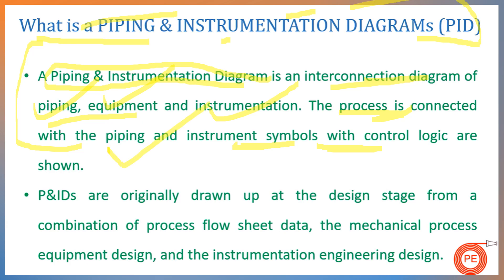It is a complete package showing how your plant will look and how your plant will work. P&IDs are originally drawn at the design stage. The basic document prepared when engineering of a process is started is your process flow diagram, and after that PFD is frozen, we go for the piping and instrumentation diagram. It is a combination of the process flow data sheet (PFD), mechanical process equipment design, and instrumentation engineering design — the basic document after which detail engineering of a process starts.